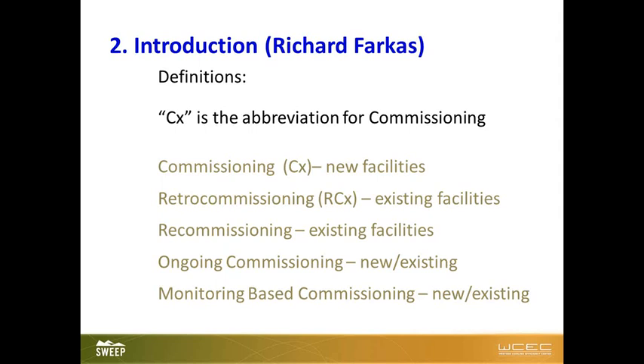Monitoring-based commissioning is basically using the DDC system as something meaningful. Historically, many building operators have used it more or less as an idiot light - for example, when your car overheats, the light comes on and tells you a catastrophic event is pending or happening. The DDC systems, if set up properly, can accumulate a tremendous amount of meaningful information - you could see from increased current curves that bearings are failing on a large motor, for instance.